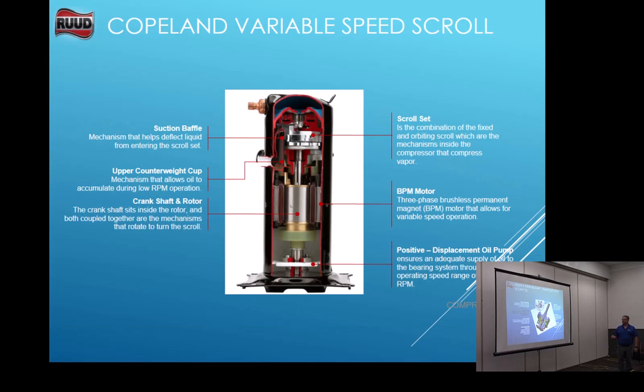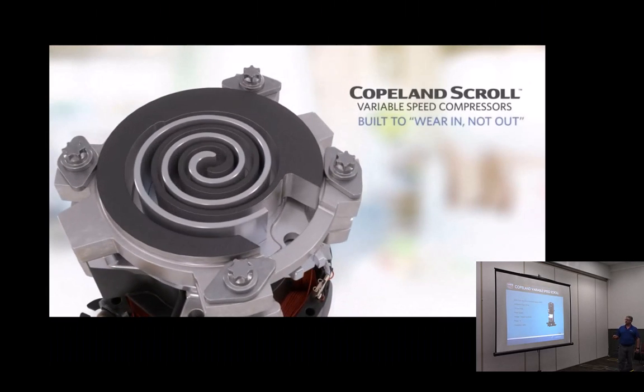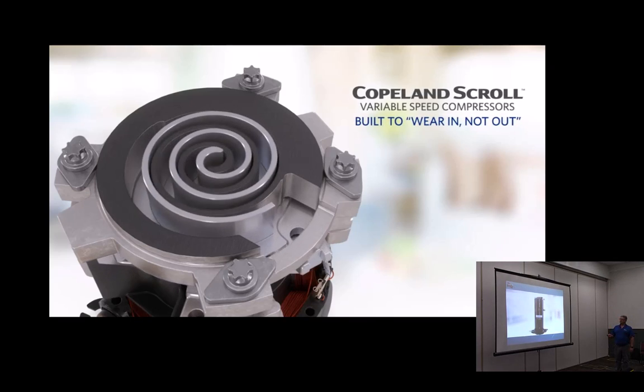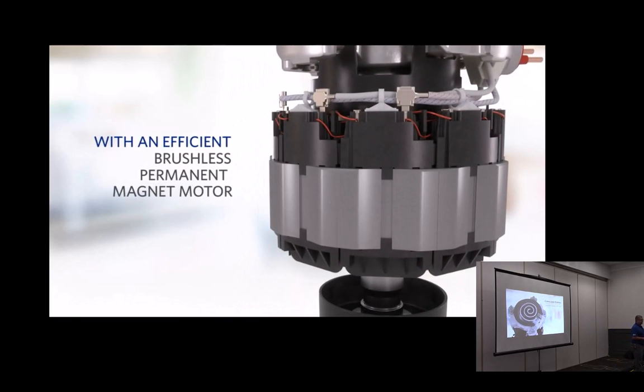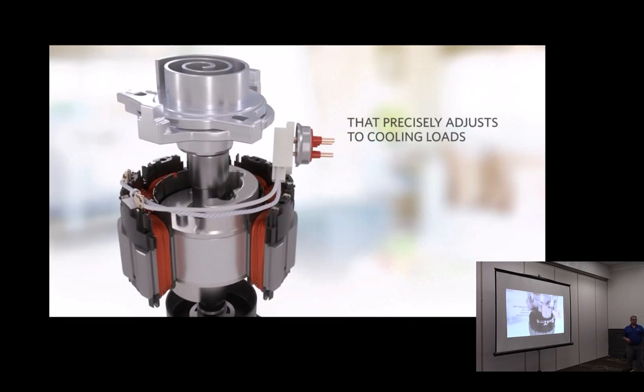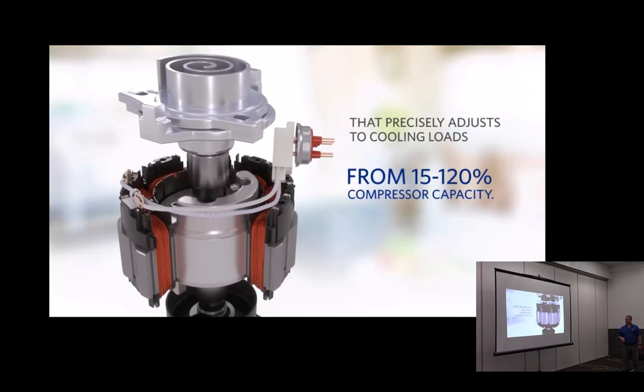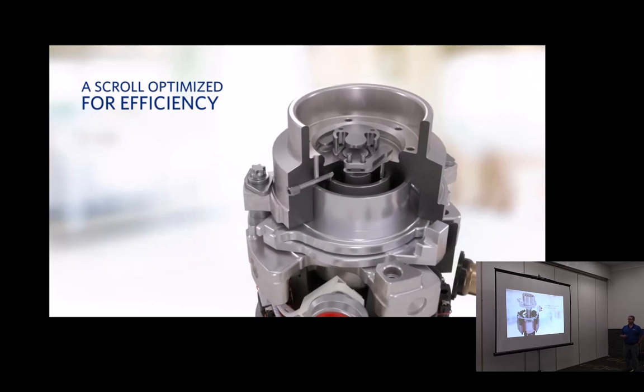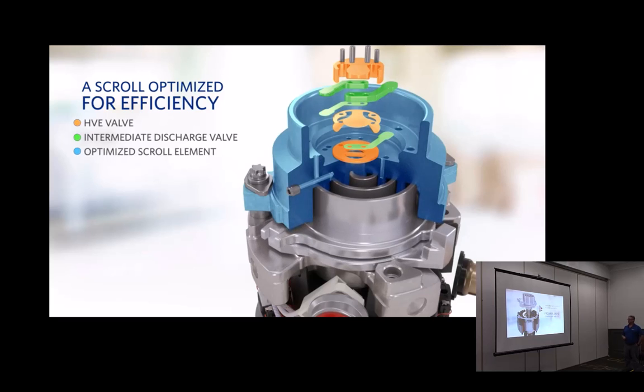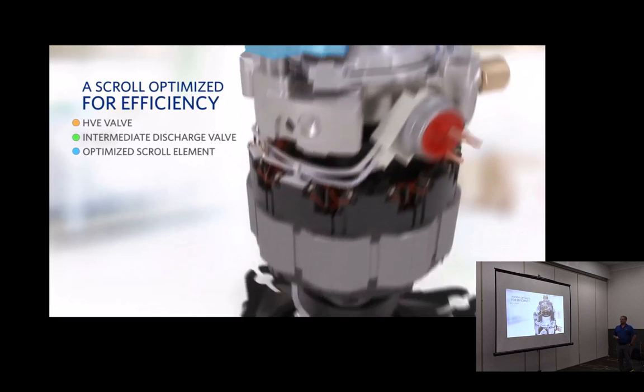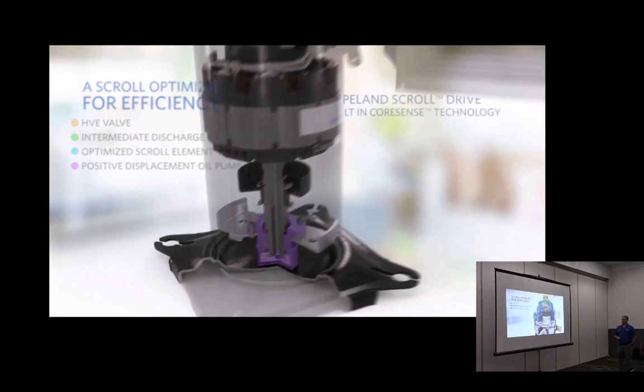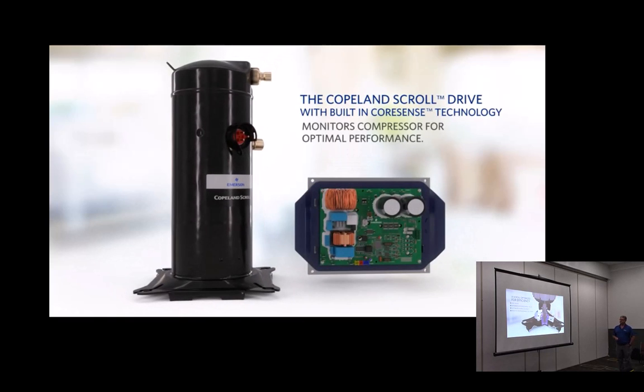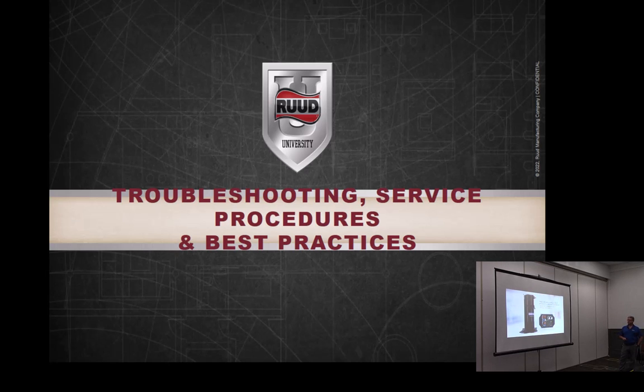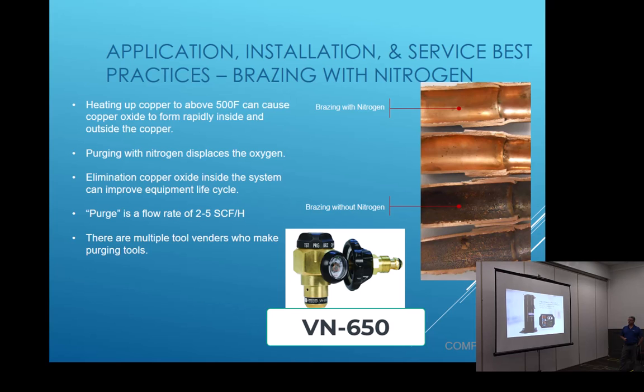Okay. This is the one that goes from 15 to 120% of capacity. So it can run up to 7,000 RPM if we're calling for it. Okay. Brazing with nitrogen, brazing without nitrogen. This is what can get in that discharge port if you don't braze with nitrogen. Okay.